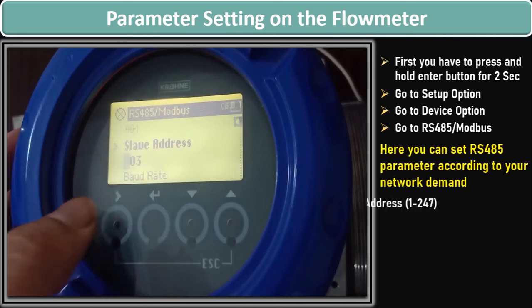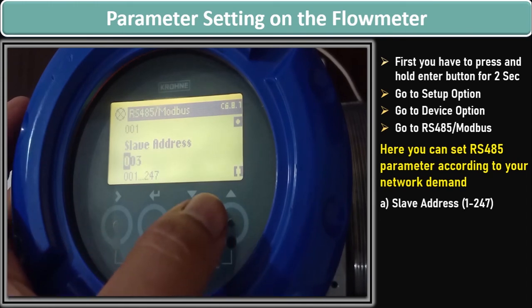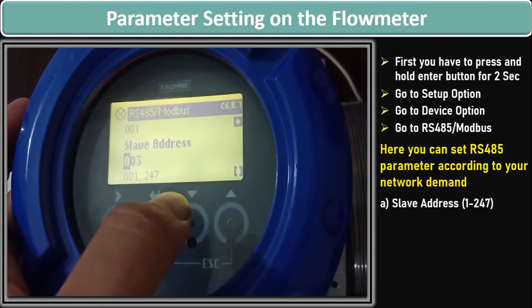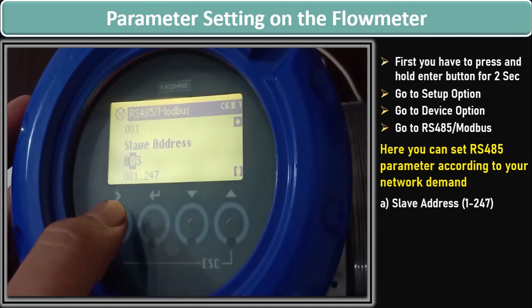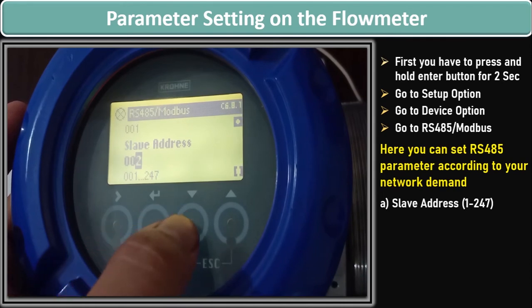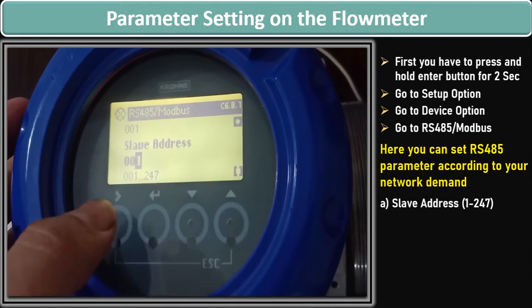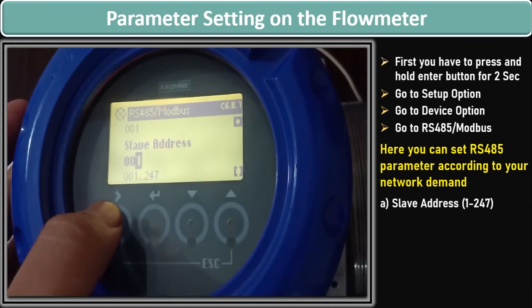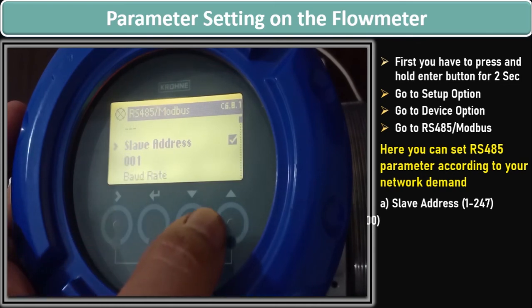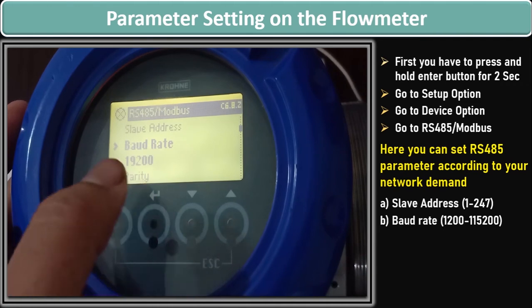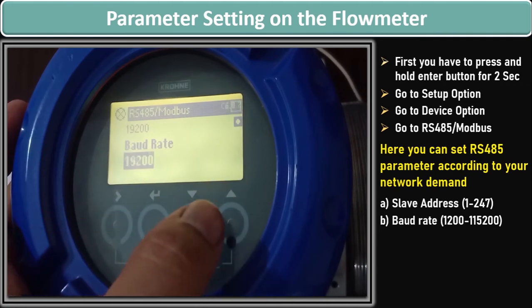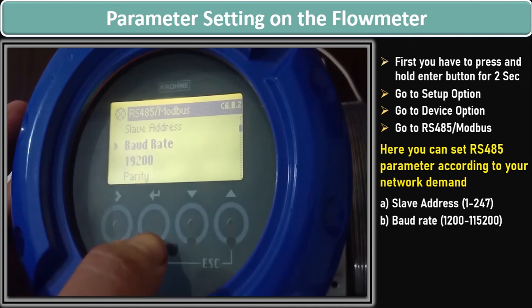The first option you see is the slave address. When you click enter on the slave address, you can change the slave address within the range of 1 to 247. You can set the slave address as per your choice or network requirement. Let's suppose I set the slave address to 1. Similarly, for the baud rate, it is given as 19200. You can change the baud rate according to your communication network needs.